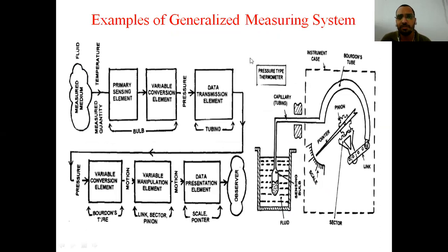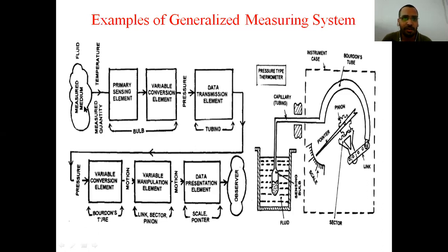This is an example of a generalized measuring system: a pressure-type thermometer. There is a fluid, a bulb, a Bourdon gauge with a link, sector gear, pinion, pointer, and scale. If you want to measure the temperature of the fluid, the bulb is the primary sensing element — it senses the temperature. The bulb also acts as a variable conversion element because the mercury inside expands due to the temperature increase, converting temperature into displacement. Due to the rise in mercury volume, pressure increases in the Bourdon tube.